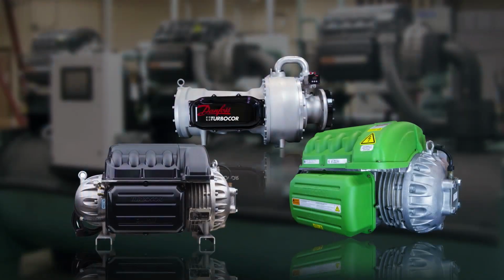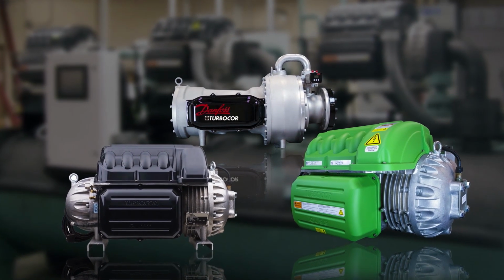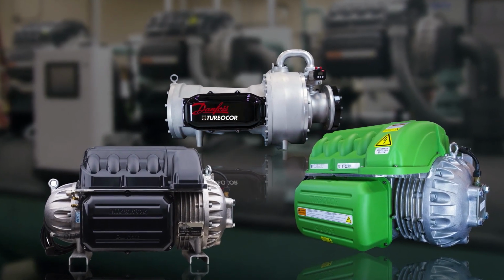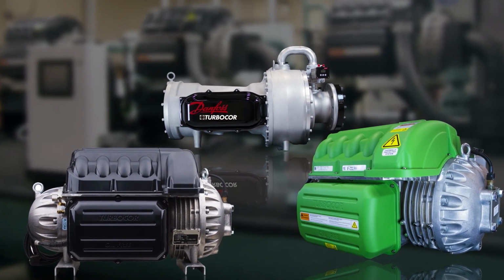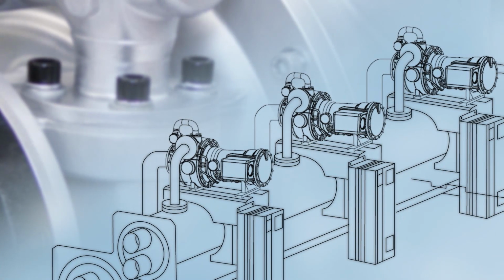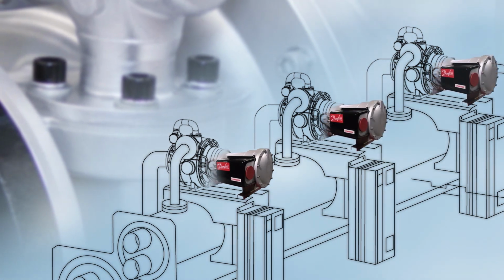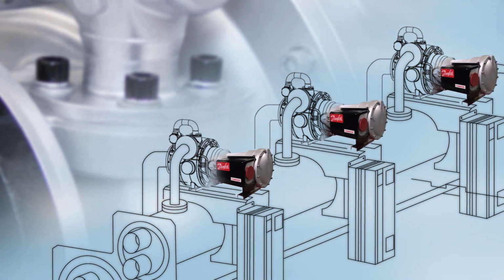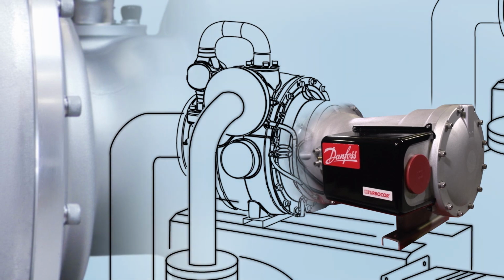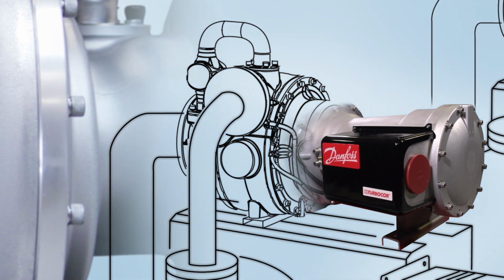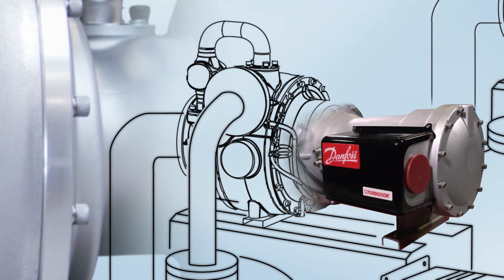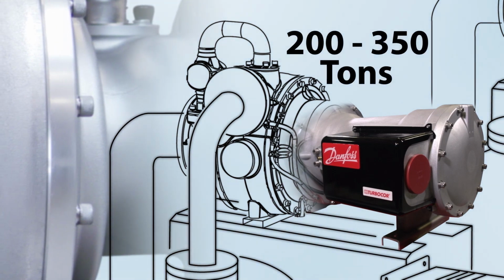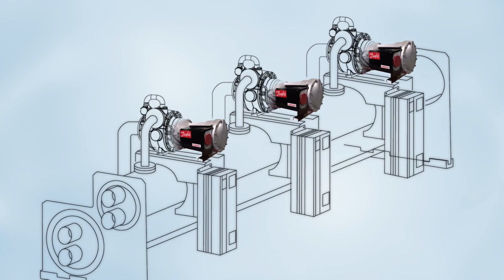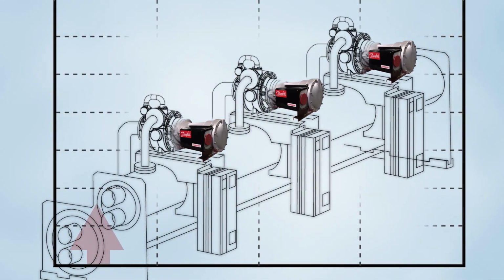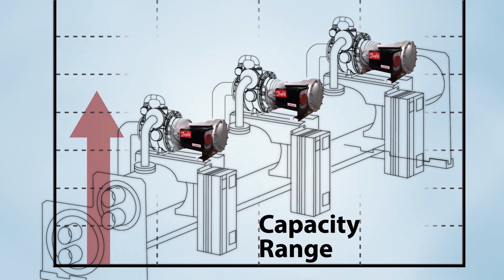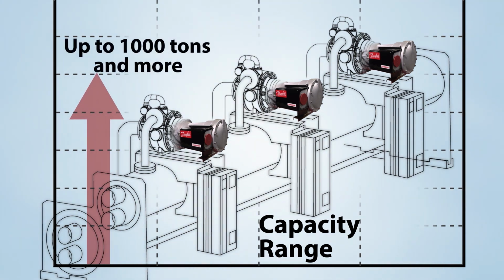Like the thousands of Danfoss Turbocor compressors already installed and which continue to operate around the world, VTT compressors are energy efficient, reliable, and have a broader operating range. VTT compressors can be applied to both multiple and single compressor chiller designs. The increased unloading range and exceptional efficiency of the VTT series enable cost-effective single compressor chiller applications in the 200 to 350 ton range without a significant performance trade-off. Using multiple VTT compressors extends capacity range of cost-effective magnetic compressor chiller designs up to 1,000 tons and more.